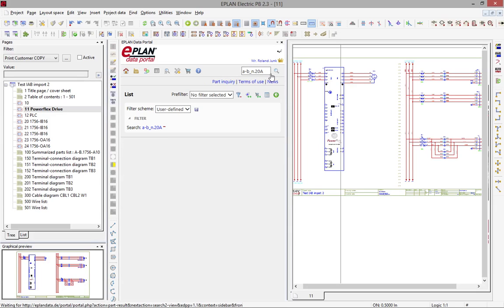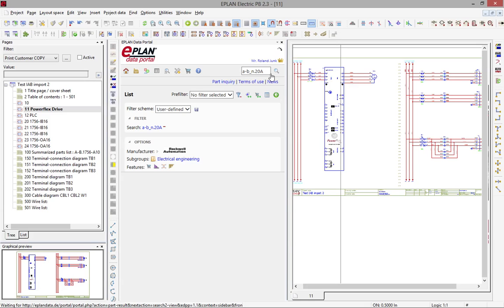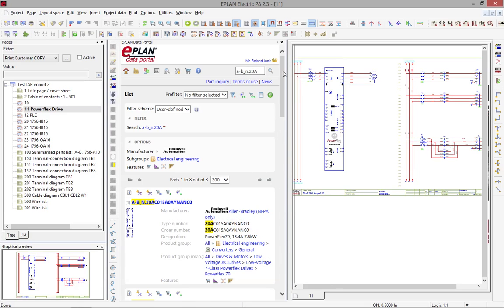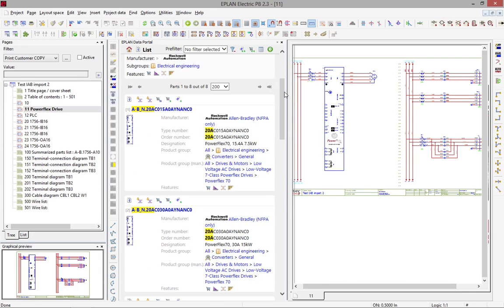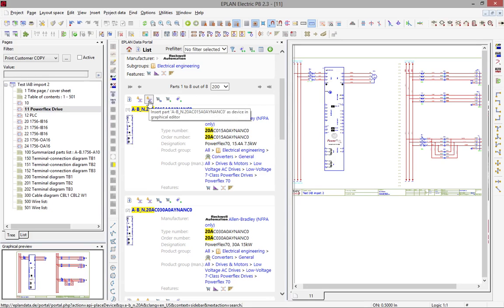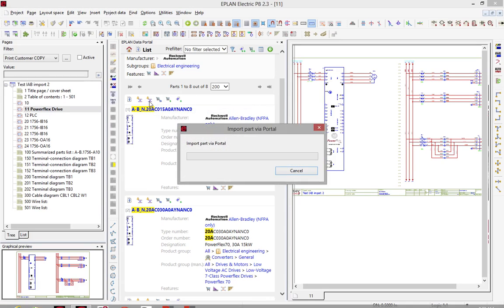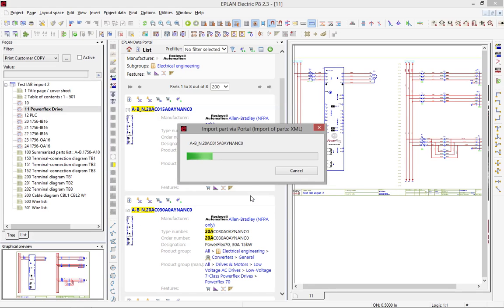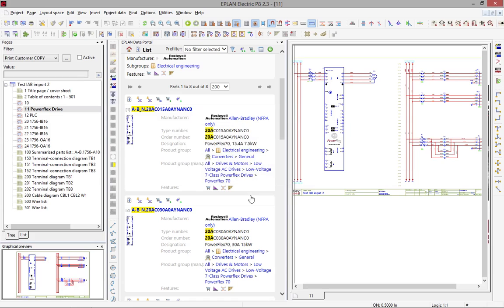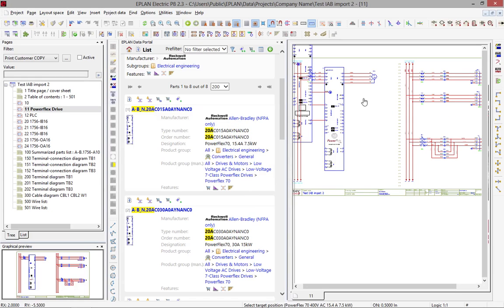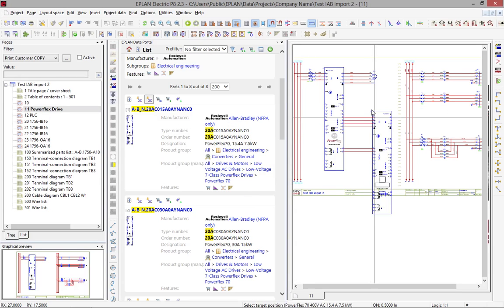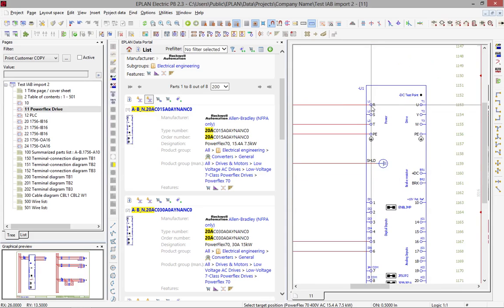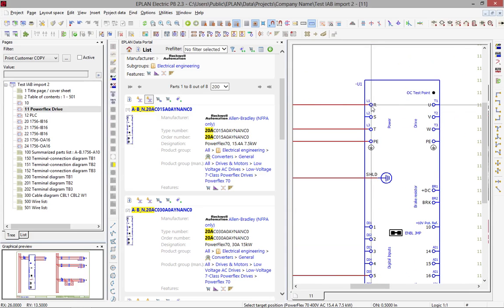Because I know that PowerFlex starts with 20A and some other numbers for the part number, for the order number. And here you can see we have one for 15 amps, one for 30 amps. And if I want to use it, all I have to do is basically just say insert part. The interesting part about this data portal is when these components are more complex, EPLAN right away comes up with the block. You can see it's attached to my mouse here. And if I zoom in, you will see all the connection designation.